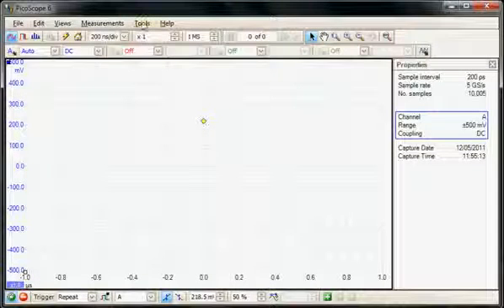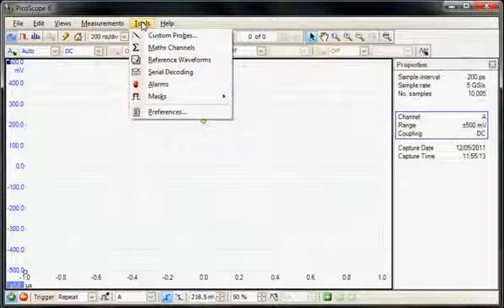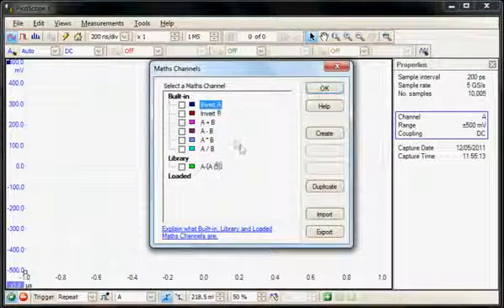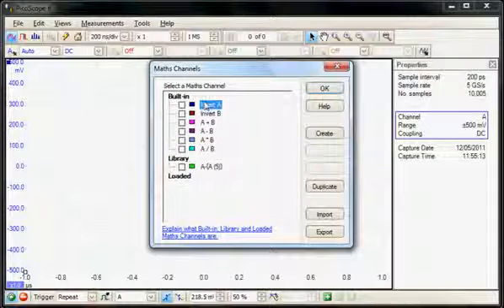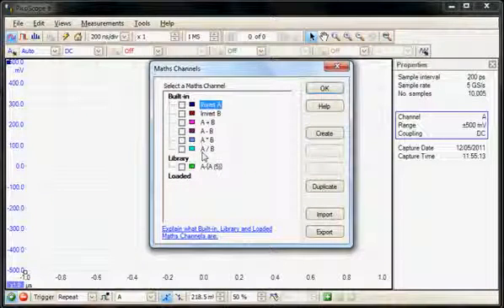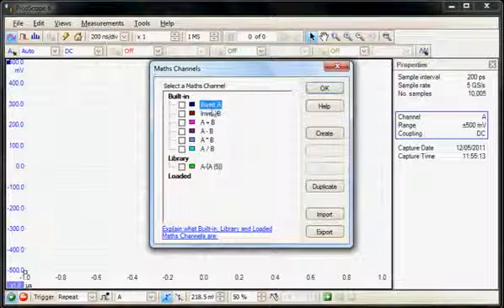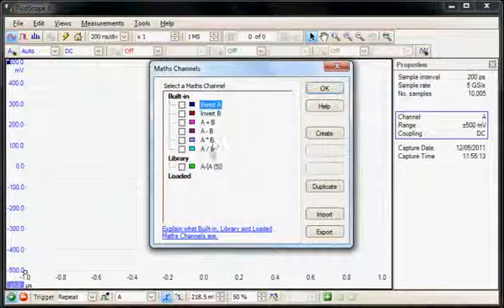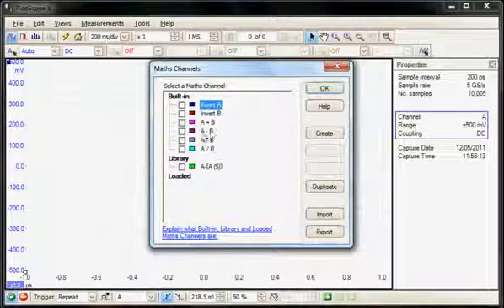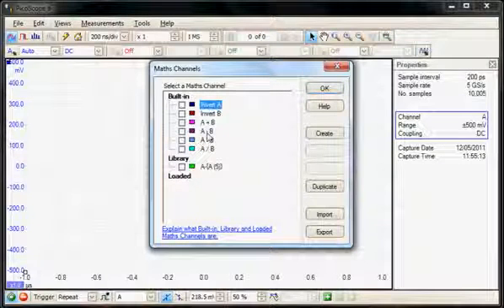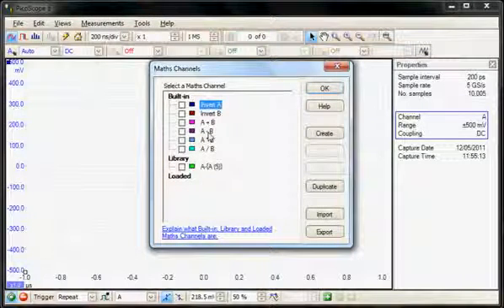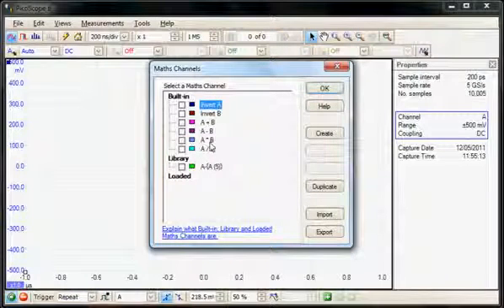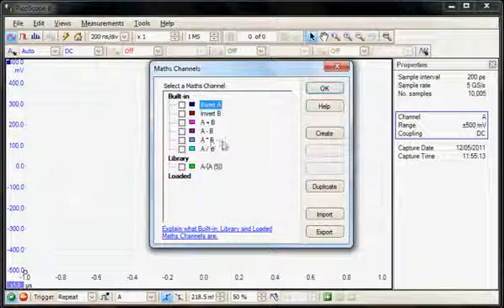Under the Tools menu are several special functions. In this section we're going to look at the Math Channel function, which comes in two sections. The first section is built-in standard functions. These include invert, adding and subtracting channels, and multiply and dividing channels. For example, the subtraction of channels could be a pseudo differential input, or the multiplication could be a voltage and a current waveform to display a power waveform.